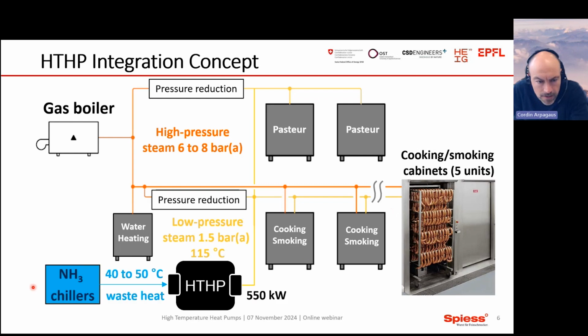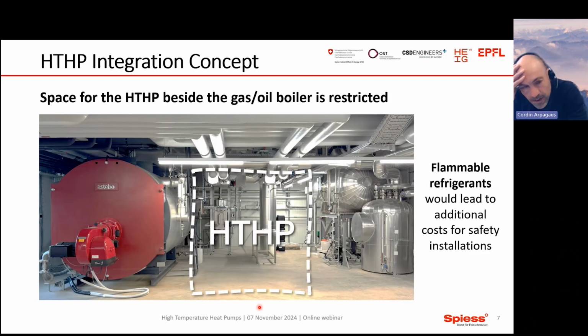And the idea would be to include a high temperature heat pump here using the waste heat from the ammonia chillers of 40 to 50 degrees for use in 115 degree or so low pressure steam. So a temperature lift which is suitable in a range that could achieve a certain COP. The capacity of the heat pump is around 550 kilowatts. So this was the status in 2023.